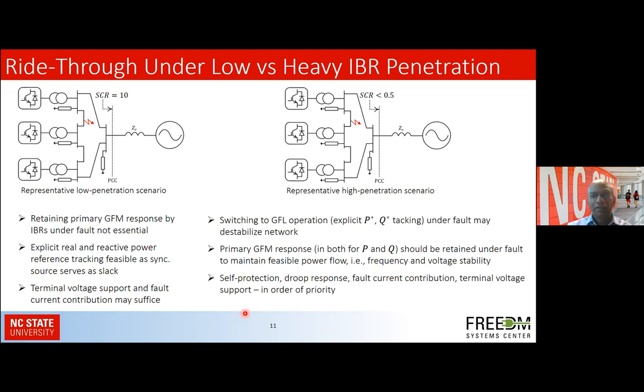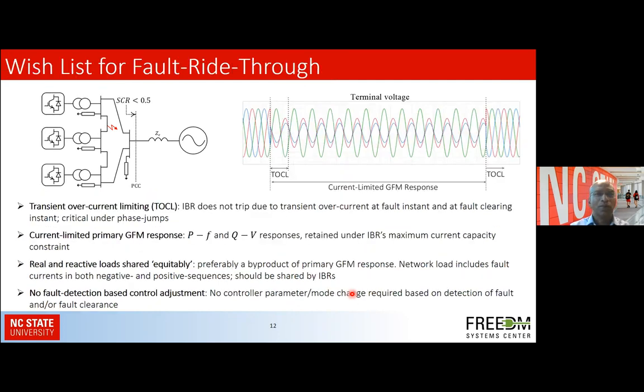So for the unit itself, in order of priority, what should be emphasized for its protection and controls is self-protection, being able to maintain the droop response, being able to contribute fault currents, and then also provide the terminal voltage support, and in terms of priority, which is in terms of its capacity as well. So the wish list that we have for fault ride-through in this context is that the IBR units must have transient overcurrent limiting. Under normal operating conditions there's an overcurrent limit, but under fault conditions, it may need to extend that limit by some percentage of the power unit to make sure that the IBR does not trip due to transient overcurrent at the fault instant.